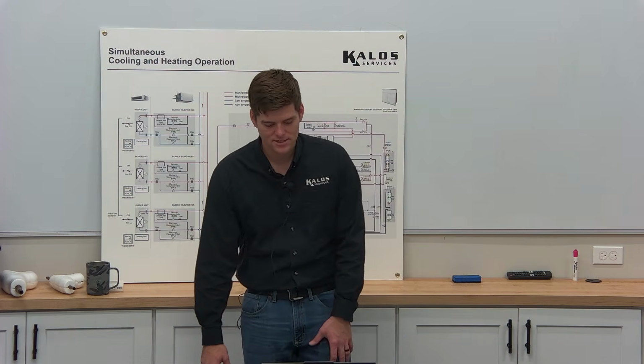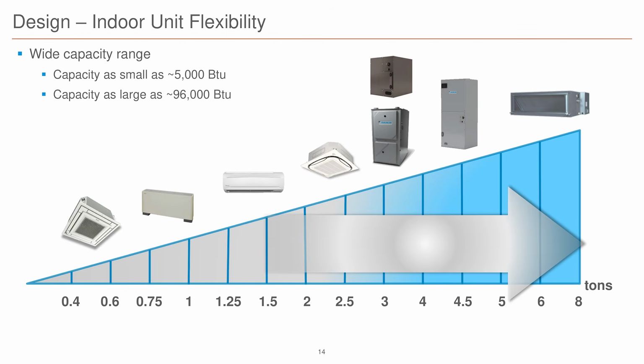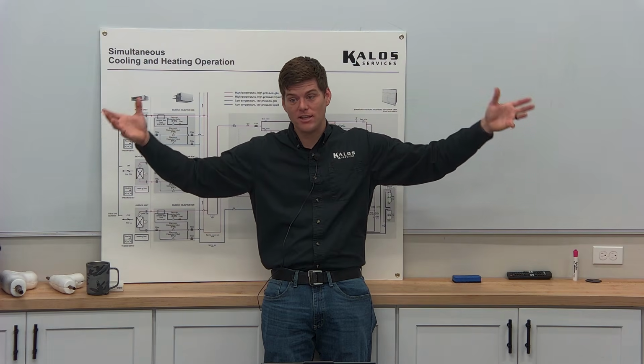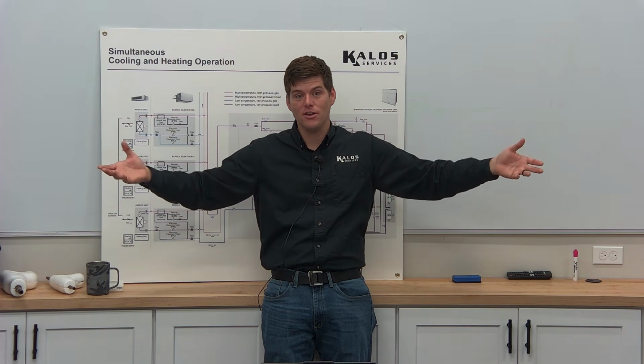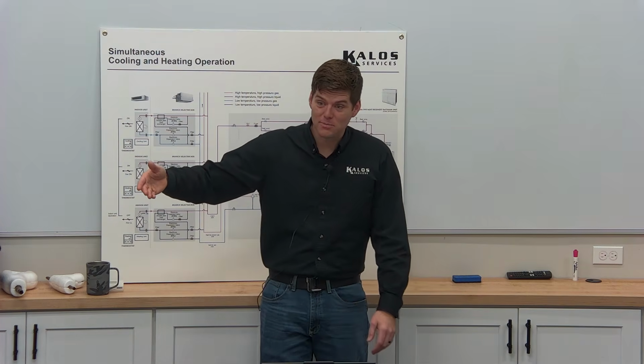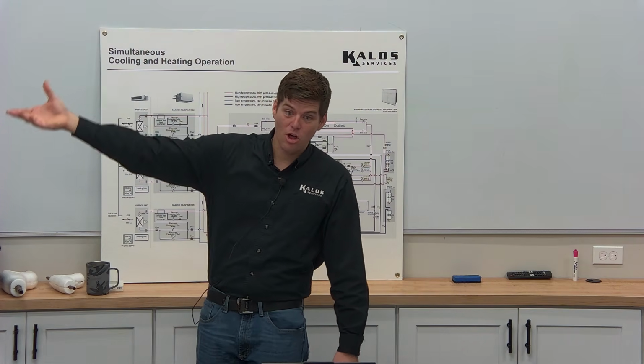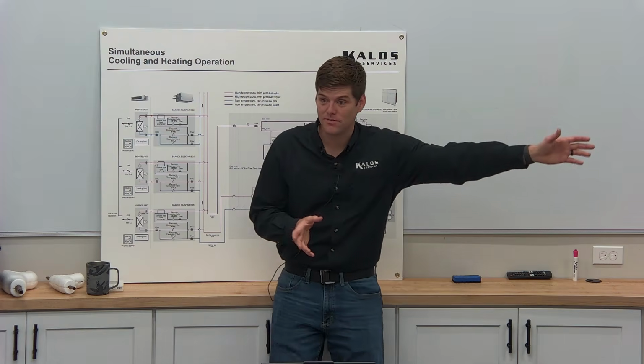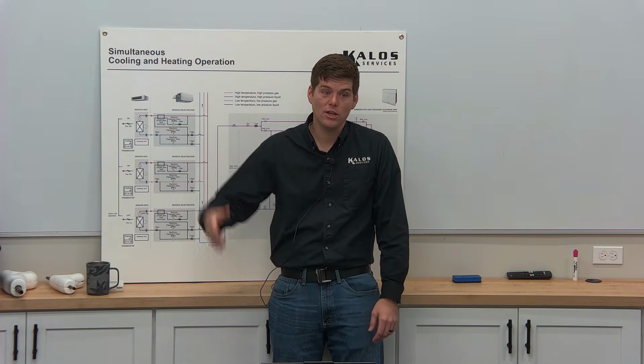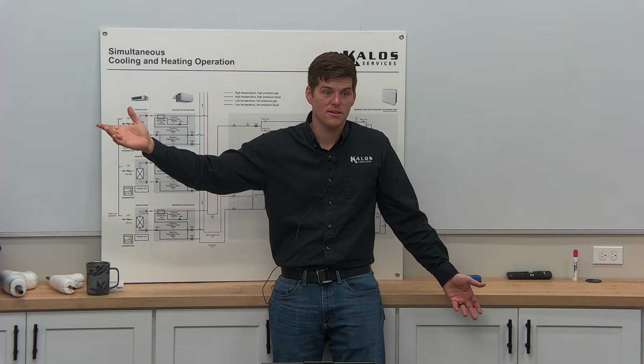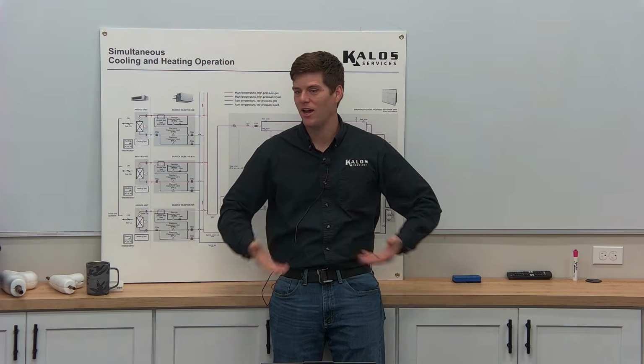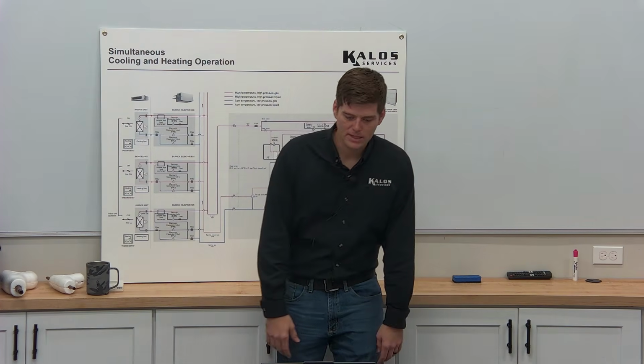Let's talk about capacity sizes. Do they really make it all the way down to 0.4 tons? Yes, they do, all the way up to 8 tons. This is the wide range and flexibility of VRF. I can go to a project that has a 20-ton system and still put a half-ton mini split in a closet or a small office and still hit all the other needs of the building itself, and only cool or heat that space when it's needed, not just dumping air all the time whenever I have to, or zoning it.